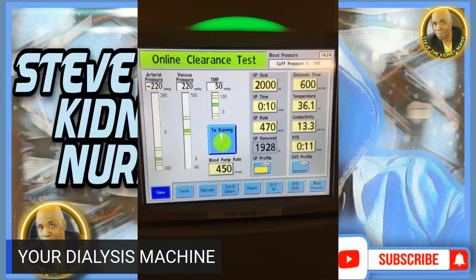Right? You've got the goal at the top. It says UF goal. You have the UF time, that means the ultrafiltration time, which means 10 minutes left. And then you've got the UF rate. That's how much fluid is being pulled off per hour, 470 cc's or milliliters. And then you go down and you have how much has been removed, which is 1,928. That's how much fluid you've removed so far. You've got 10 minutes to go, and you're trying to pull off the goal of 2,000. You should be able to make it to the 2.